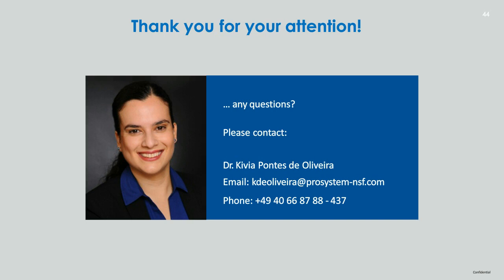Okay, thank you. I've got a question here asking, are there differences between a pre-market evaluation report and a post-market evaluation report? A pre-market evaluation report, as the name says, is a clinical evaluation report prepared before the device enters the market. This report is part of the technical documentation and should be submitted to the notified body together with other documentation for market approval.